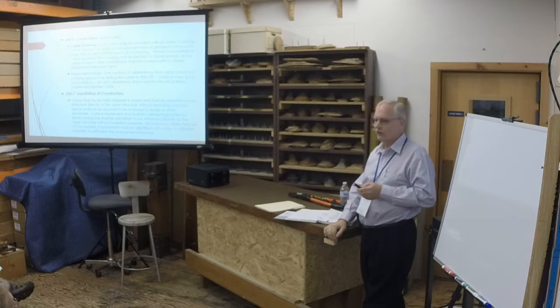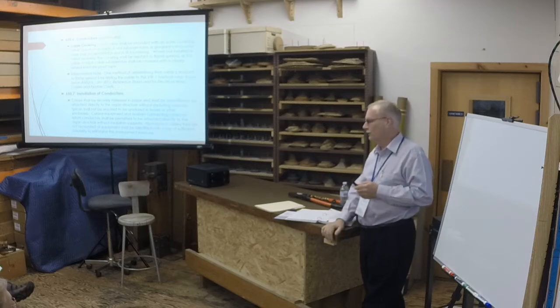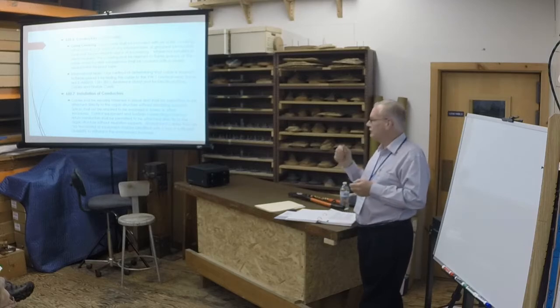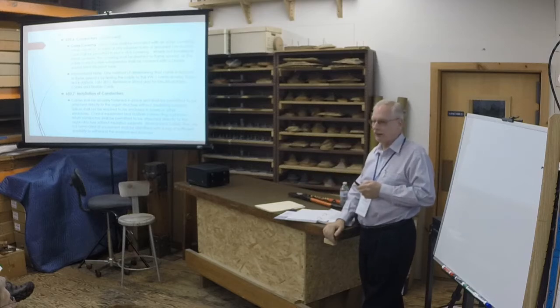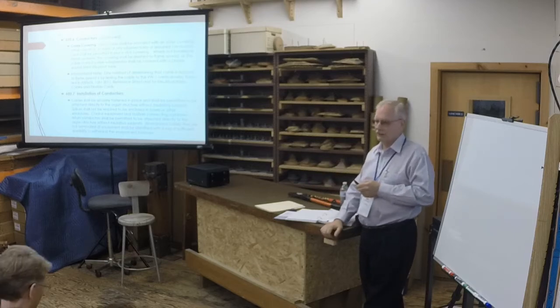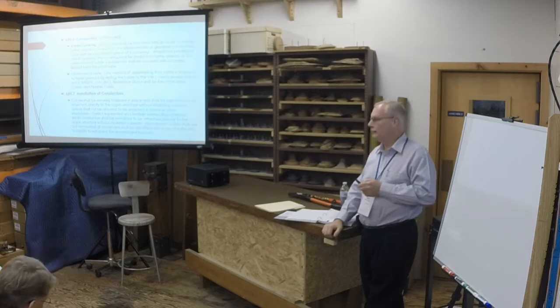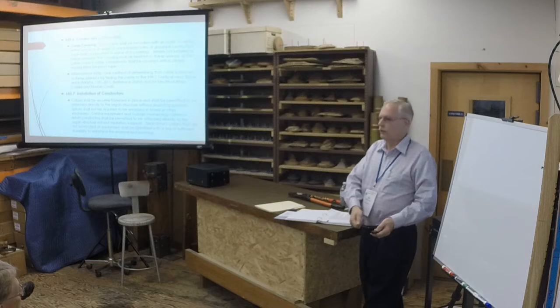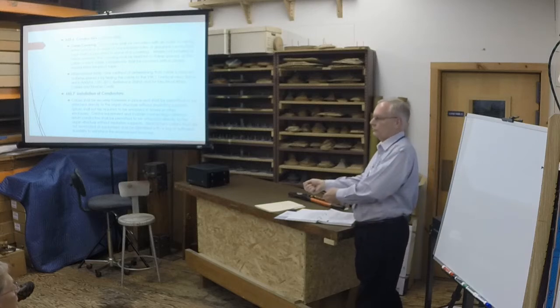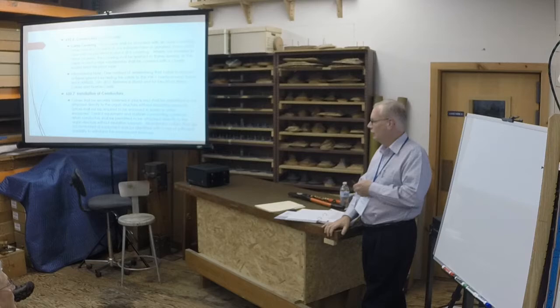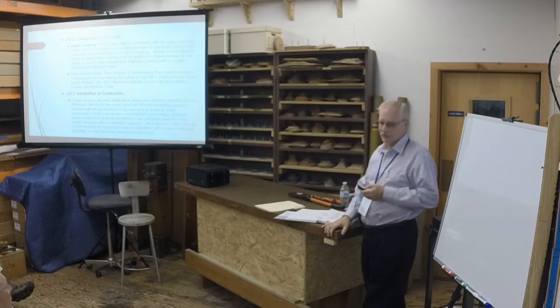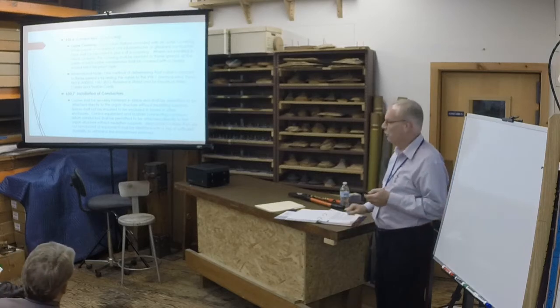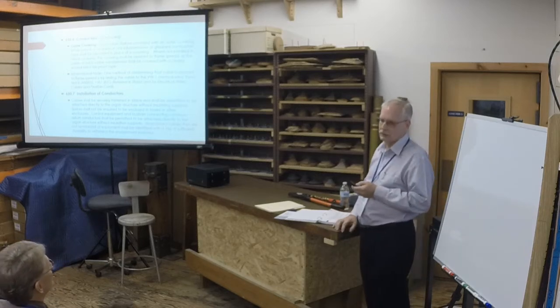And if you don't know where the other end is, get yourself a toner and figure it out. Because again, if there is an incident and somebody goes looking for a reason, your untagged cable could become, 'oh, well, I tied onto that cable, I didn't know what it was for, and the other end started a fire.' Abandoned cable should not be live under any circumstances. Just because you have one end doesn't mean you have the other end. Both ends need to be tagged and noted as abandoned.